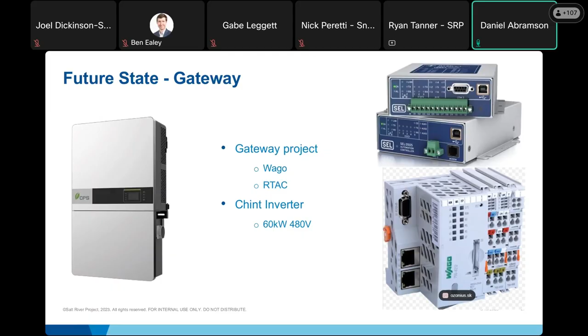The long-term win isn't just one working inverter, but a repeatable integration pattern other projects could plug into. So one plan, and kind of the vision, could be to publish something like a standard point sheet aligned to the MESA required points and the core control modes we support. That sheet could become a standard sheet that we require, with a model looking to require DER developers to deliver something like an RTAC or gateway pre-programmed to that point sheet and connected to a site controller.